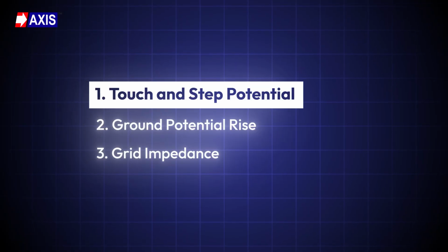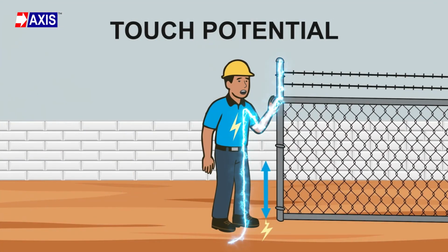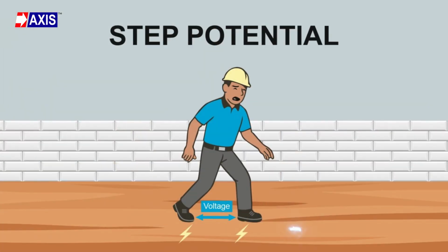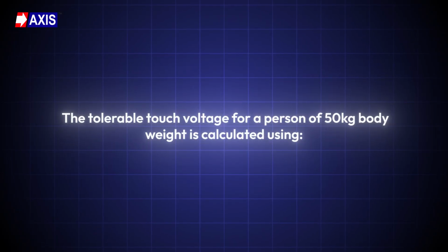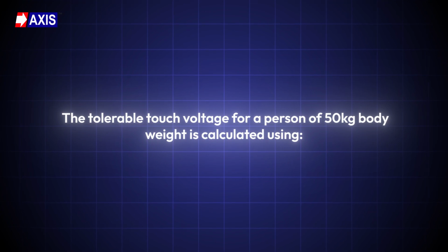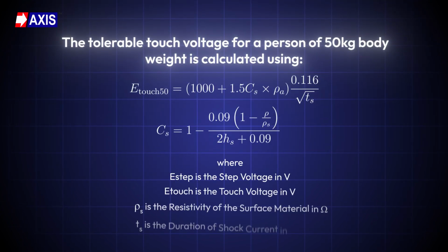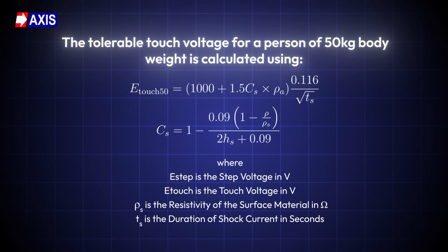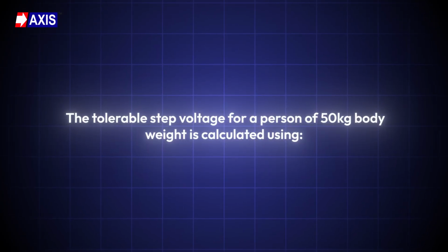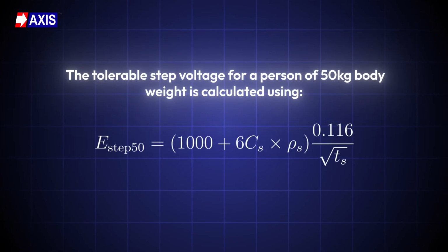Now, let's understand these risks in detail, starting with touch and step potential. If you touch a conductor while standing on the ground, the current travels through your body. This is touch potential. If your feet are apart, voltage differences between them drive current through your body. This is step potential. The tolerable touch voltage for a person of 50 kg of body weight is calculated using this formula. Similarly, the tolerable step voltage for a person of 50 kg body weight is calculated using this formula.